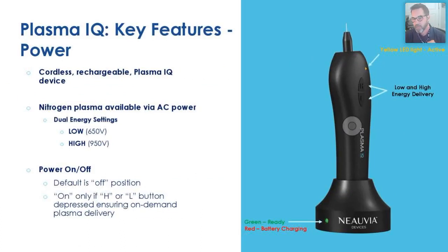So here again, it is sitting on the charging station. High power and low power. This light here will only become activated once you have the energy being active. So you are responsible solely for the delivery of the energy. I'll show you a video of what that looks like in just a moment. If you don't push the button, it's not going to deliver energy, and it will deliver energy as long as you have the button pushed and the probe close to the skin, about 1 millimeter away. We do know that our device will provide 650 volts of energy at the low power setting and 950 volts of energy at the high power setting.